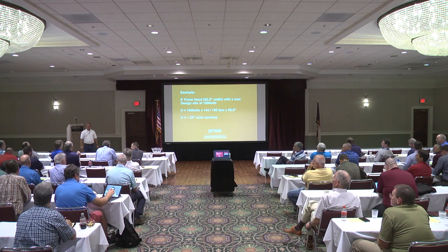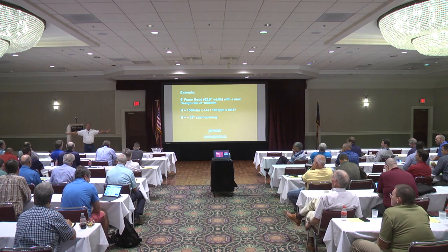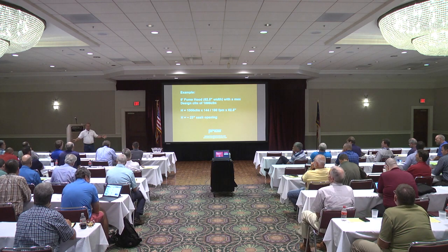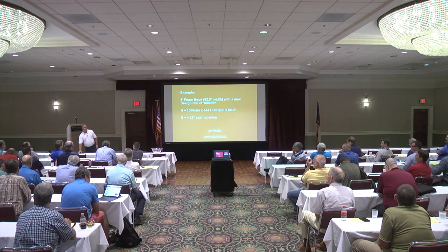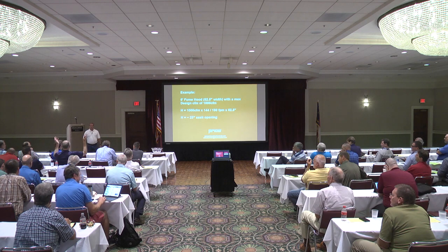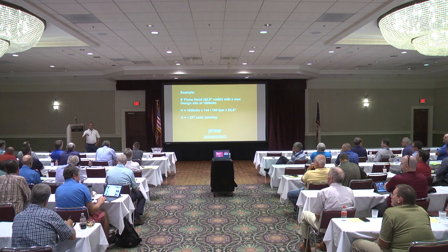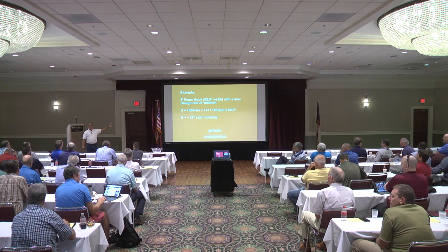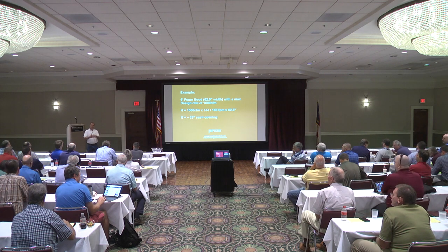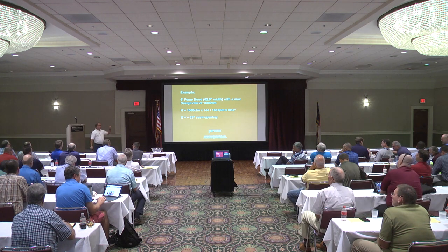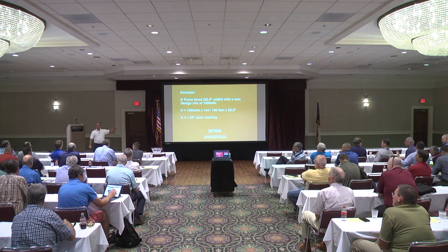I'm saying, should it be a design RFI from an energy standpoint, since 18 inches is say 800 CFM? You're overthinking it. He put out a design. We walked onto the job together, and this is our design. But we're also professionals, and we should be asking design RFI questions before we just go exhaust 1,000 when our fume hoods really only need 800. But you're saying that from an energy perspective, and the design engineer had another reason for this design. I'm not going to disagree if you want to ask the question, but you've got to know that this is going on in order to ask the question. And that's why I brought it up.